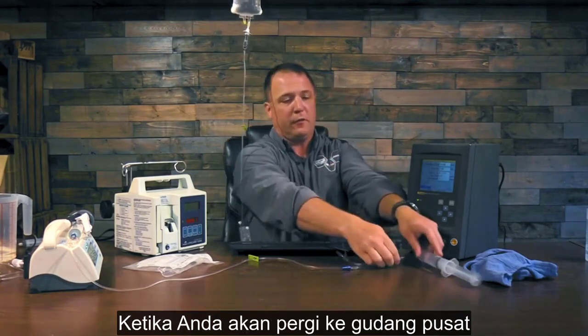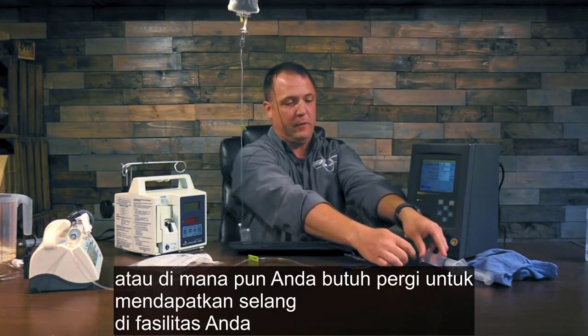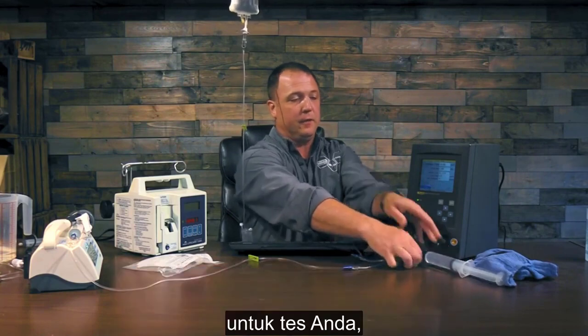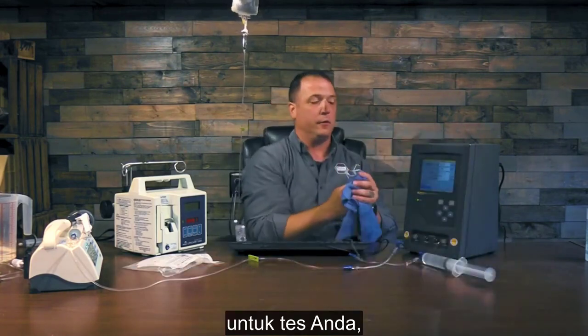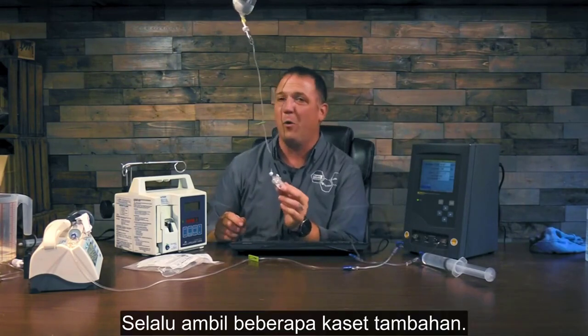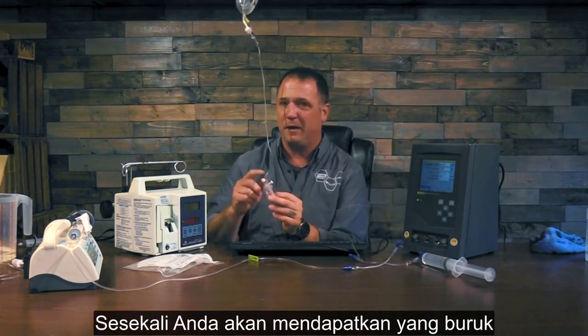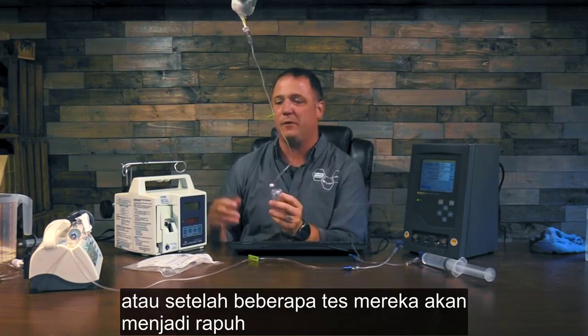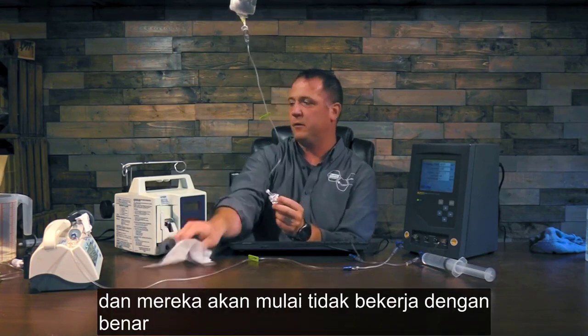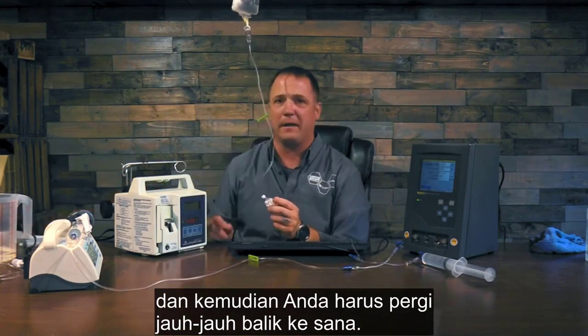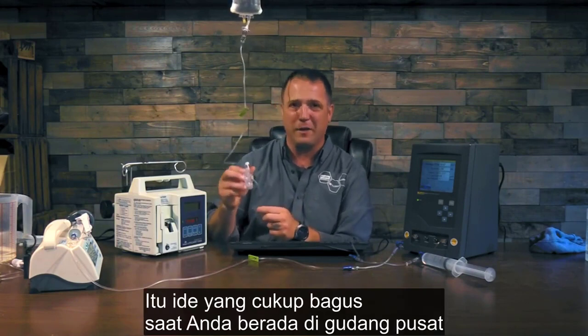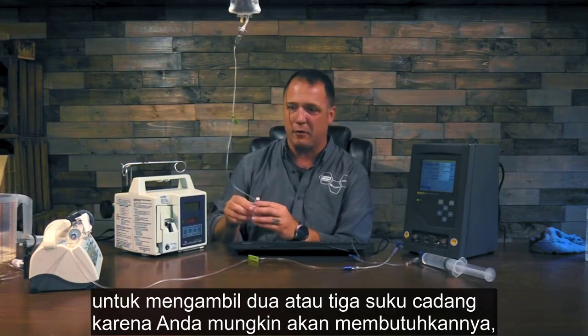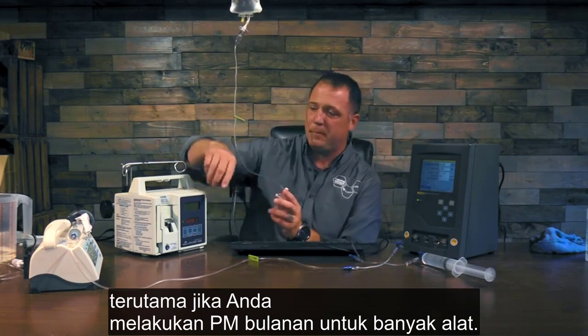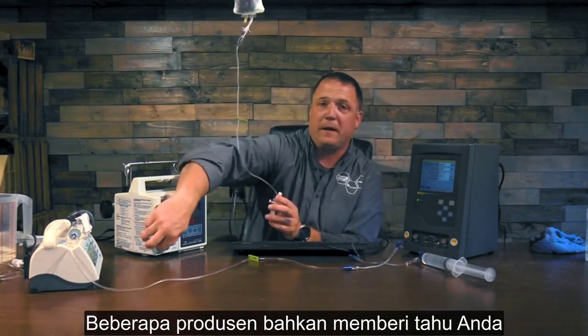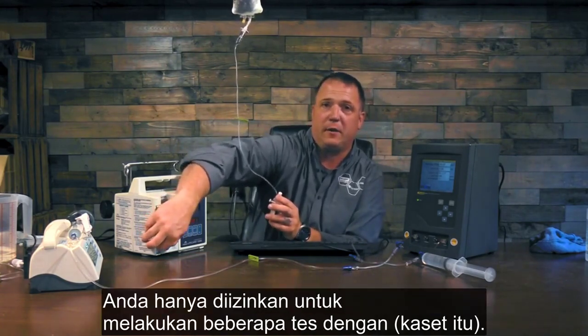When you're going to go to Central Supply, or wherever you need to go in your facility to get your tubing to set up your tests, always get a few extra cassettes. Every now and again you'll get a bad one, or after a few tests they'll get brittle and they'll start to not work right, and then you have to go the whole way back down there. So it's a pretty good idea while you're down there to get 2 or 3 spares, because you'll probably need them, especially if you're doing a high PM month. Some manufacturers even tell you you're only allowed to use so many tests on it.